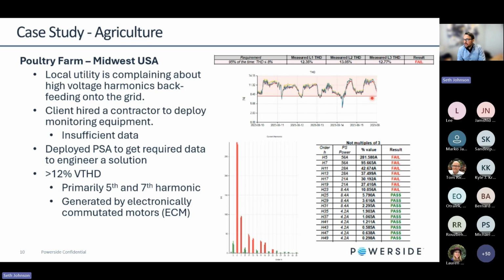And they came to us and said, well, no, the manufacturer states that these ECM motors meet 519 compliance standards. And first we go back and say, well, 519 is not an equipment standard, it's a point of common coupling standard. And so the issue came into play when they had 200 or more of these on each of these 6 different feeds, which is why you see a voltage distortion so significant.